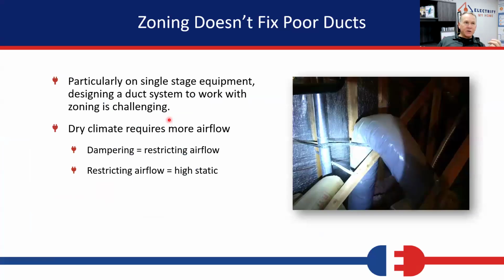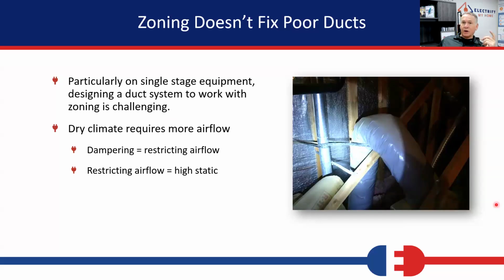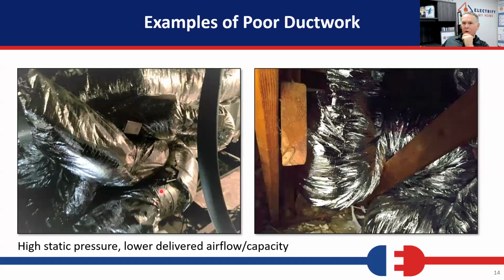Okay. Zoning doesn't fix bad ductwork. If I have bad ductwork in the house and/or a bunch of small ducts coming off the system, that's going to be a net negative benefit, because we've already got high static pressure in the system, and then we're going to add zones to it. It's going to make it even worse. So, high static pressure, lower delivered airflow.